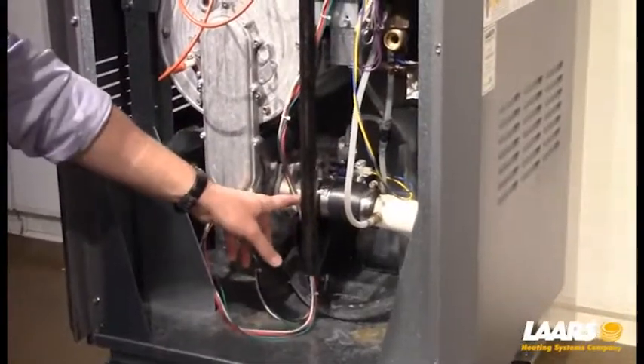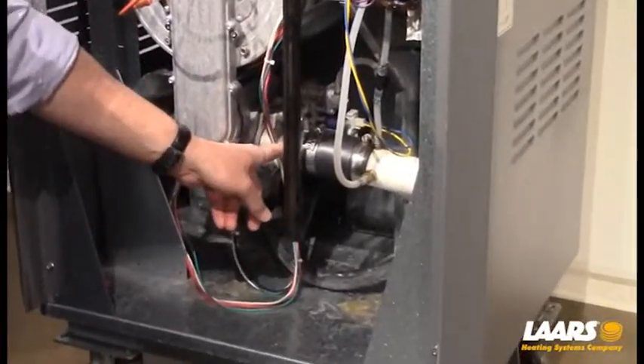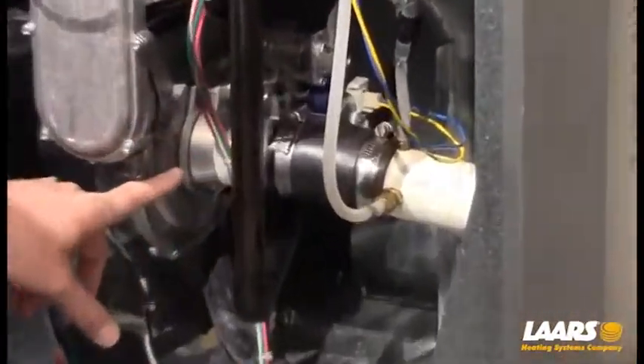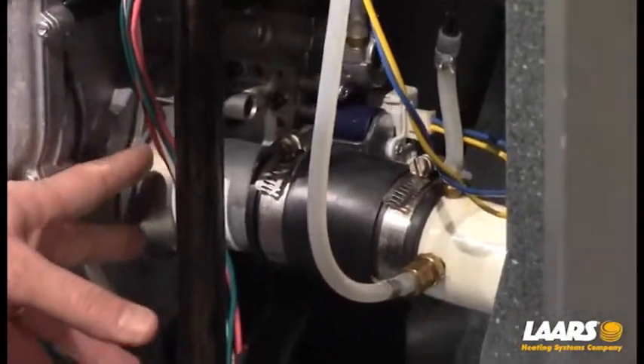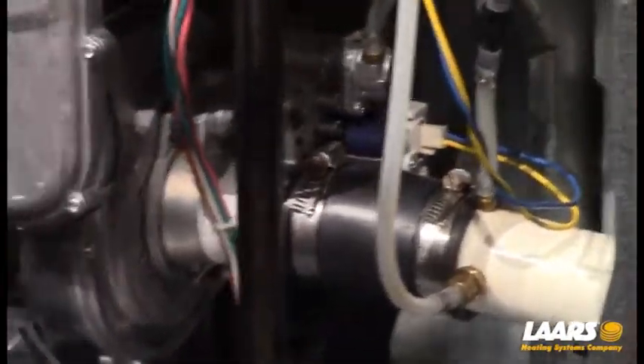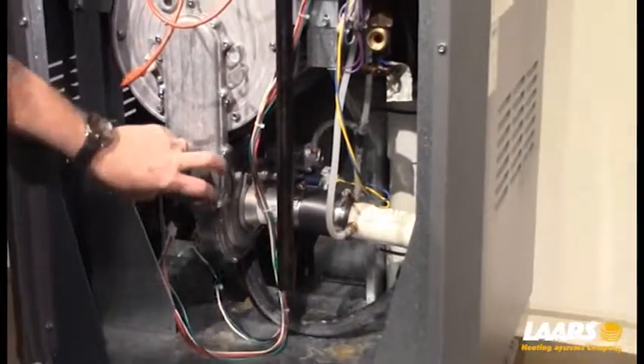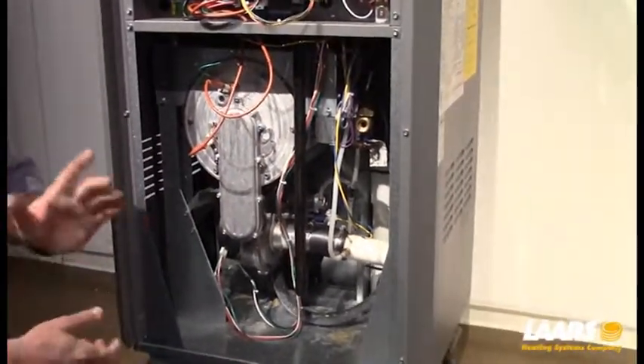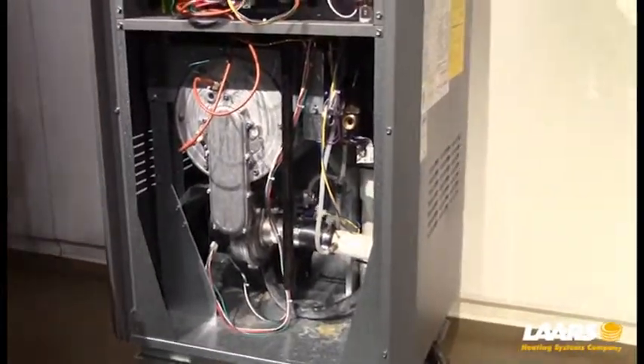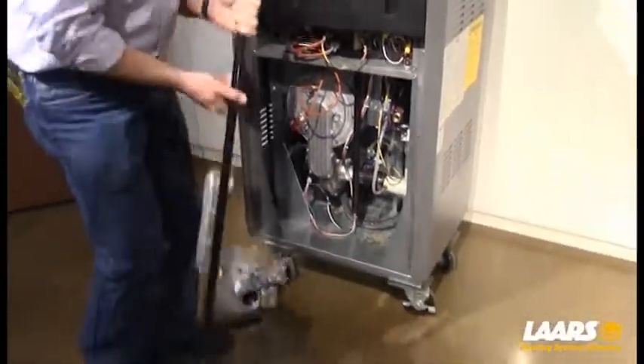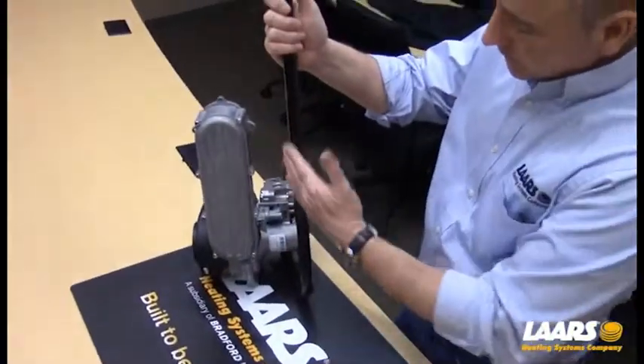But prior to removing these nuts, we also have the fresh air intake that comes into the venturi, the gas valve is attached to the venturi, and the venturi is attached to the blower. So we're going to disassemble this here and pull this out all as one piece with the blower, arm, and burner head. Prior to doing that, I just want to show you what I have as a demonstration here. So the orientation is the same.